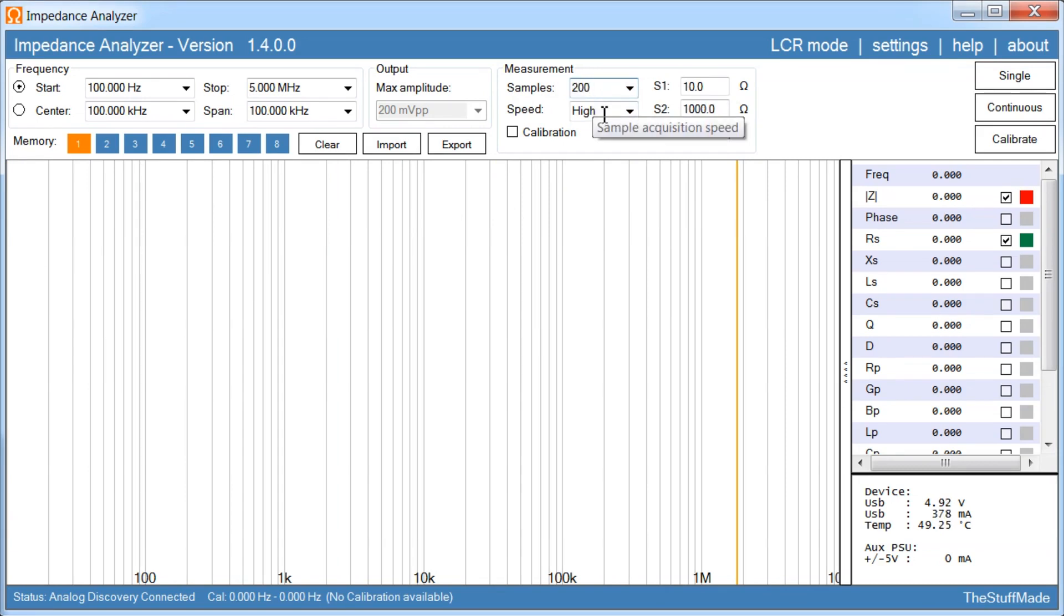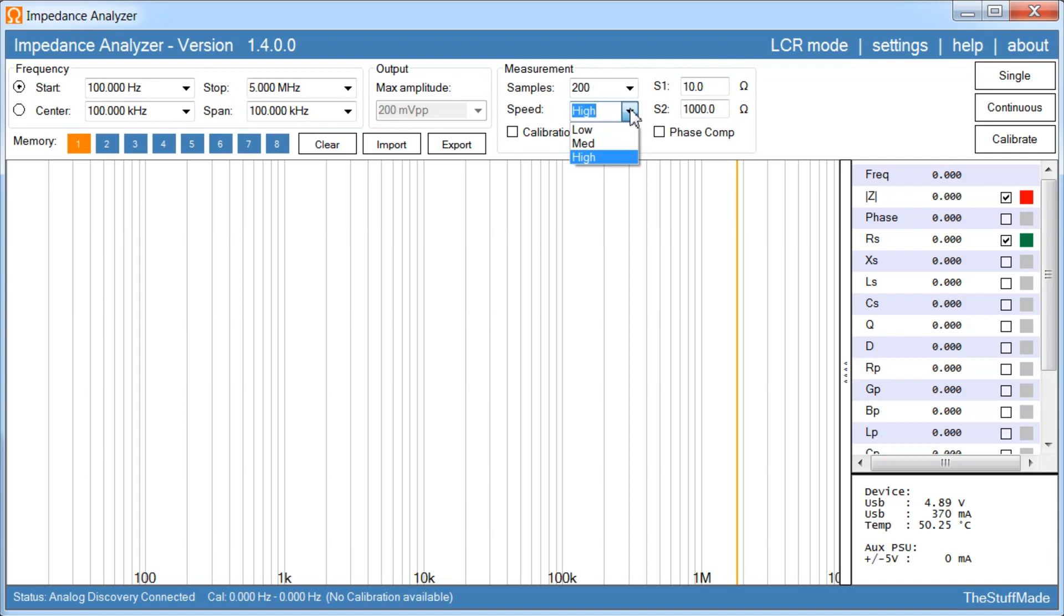And we have speed. This was kind of a little bit experimental, I don't think there's any reason to set it to anything other than high. The lower speeds will capture more waves and give more averages, but in my experience it doesn't really make much difference, I usually just keep it on high speed.